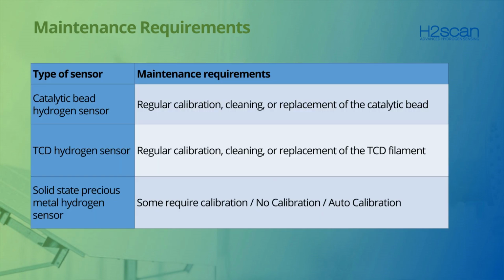So the maintenance required by hydrogen sensors is a key factor in your total cost of ownership. When looking at catalytic bead hydrogen sensors, they have a very high maintenance requirement. The frequency of calibration will depend on the operating environment and the required accuracy of the sensor. These sensors should also be cleaned and replaced according to the manufacturer specifications. In my experience, oftentimes we see replacement happening every 3 to 5 years. TCD hydrogen sensors require regular calibration to ensure their accuracy. Again, the frequency of calibration will depend on the operating environment and the required accuracy. And also the TCD filament should be cleaned and replaced according to manufacturer's guidelines to prevent contamination.